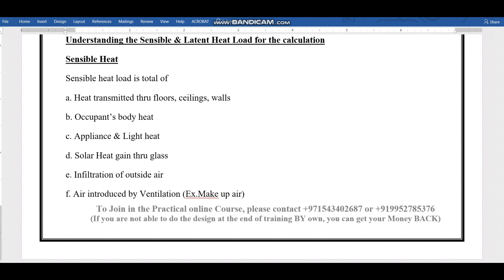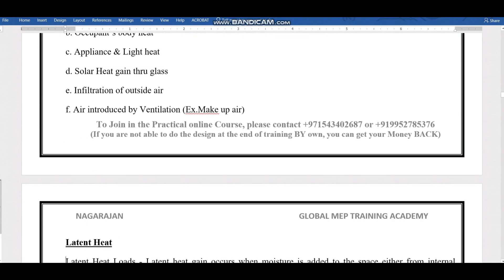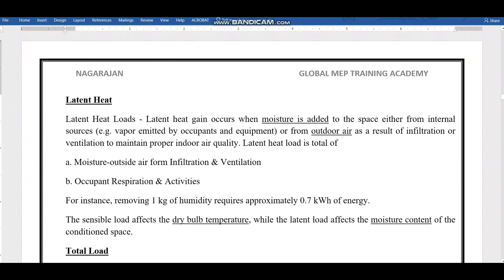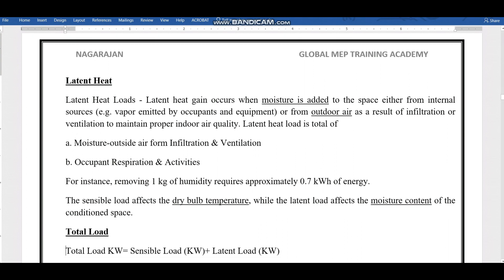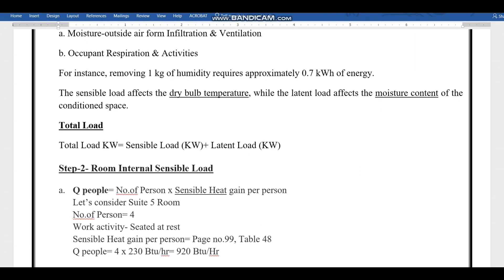As mentioned in the previous video, sensible heat is caused by heat transmitted through floors, ceilings, walls, equipment, body heat, appliances, lighting, solar heat through glass, infiltration, and ventilation makeup air. Latent heat comes from equipment and outside air through infiltration and ventilation. For infiltration specifically, the latent load tends to be higher while the sensible load is lower.